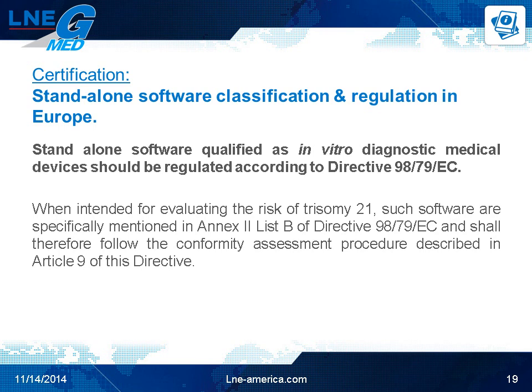Standalone software qualified as an in vitro diagnostic medical device should be regulated according to Directive 98/79/EC. When intended for evaluating the risk of trisomy 21, for example, such software is specifically mentioned in Annex 2 List B of Directive 98/79/EC, and shall therefore follow the conformity assessment procedure described in Article 9 of this Directive. Directive 90/385/EC does not define different classifications; if this directive is applicable for standalone software, the route is the equivalent route to an active implantable medical device directive.